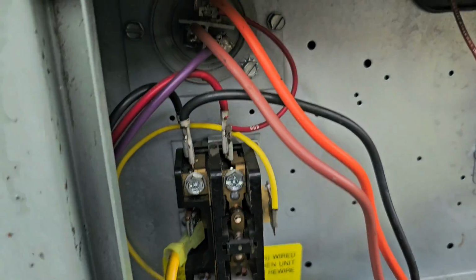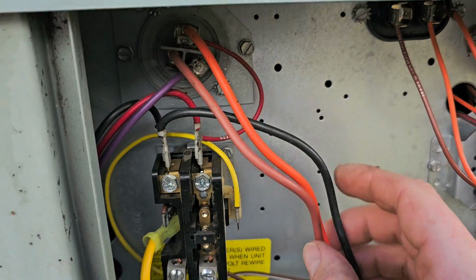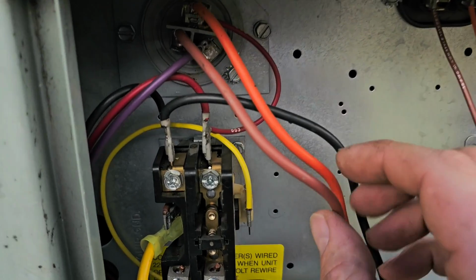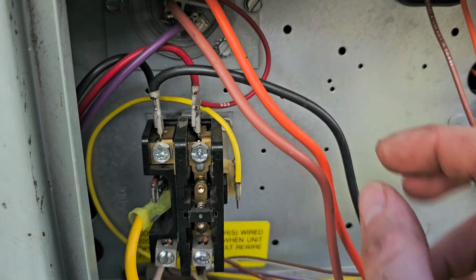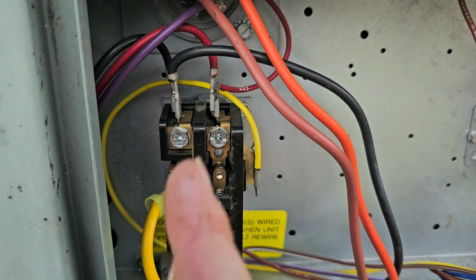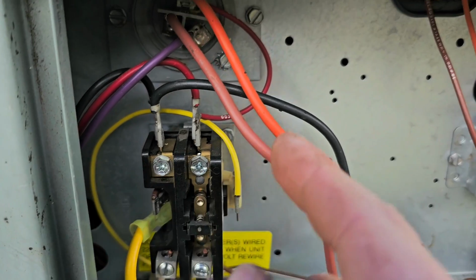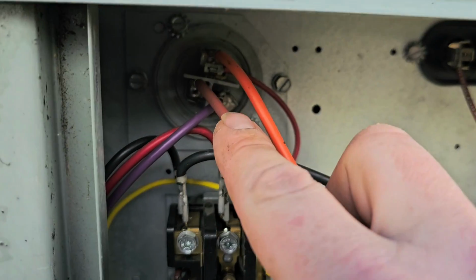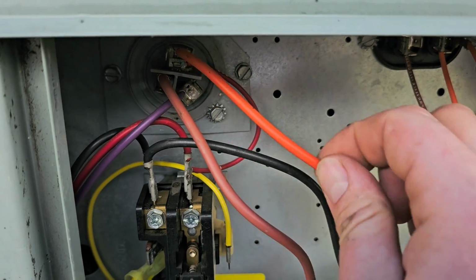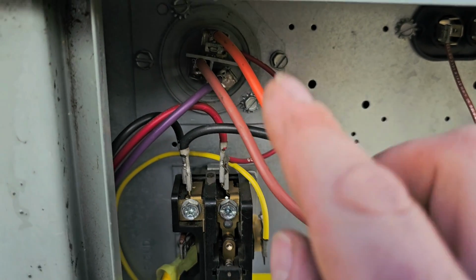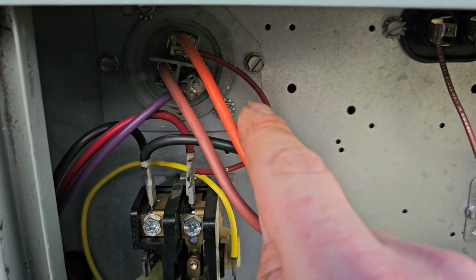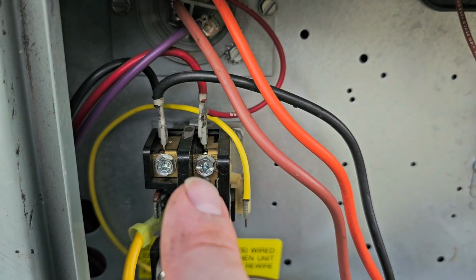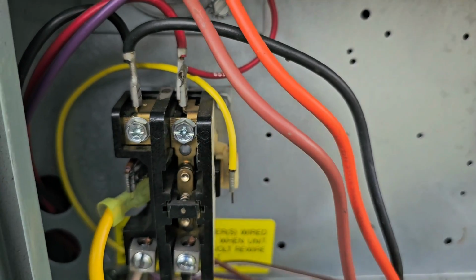Also wired in the outdoor fan motor because we had to unplug those wires to take the top off. There were 3 wires. We got a black wire going to the load side, one side of the load side of the contactor, and then we got the brown wire going to the fan terminal, the dual capacitor, and then we got the orange wire going to the common terminal of the dual capacitor, which connects to the other side of the load side of the contactor.